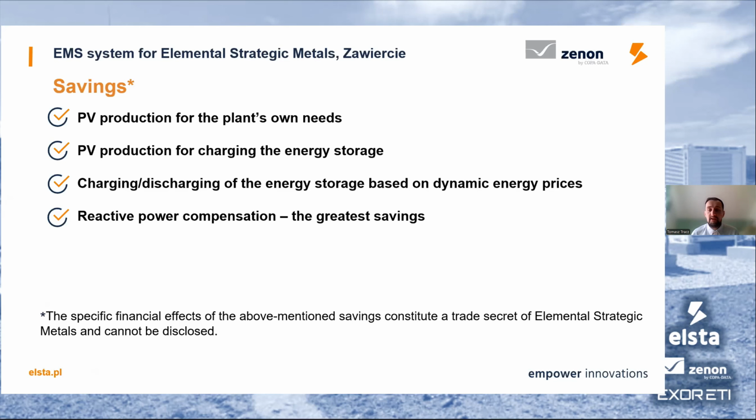But I would say the outcome which gives the greatest savings is actually reactive power compensation, which when we've checked, we cannot give exact numbers. But comparing all these obvious savings which were planned, the biggest savings from this project actually are from compensation of the reactive power. And this may be surprising for some of you listeners, but actually this is the factor which is not always taken into account when you are calculating return on investment.